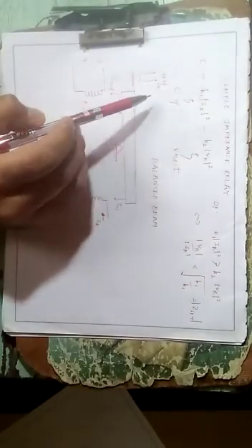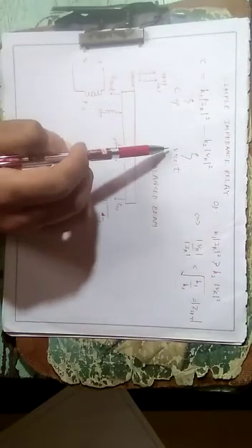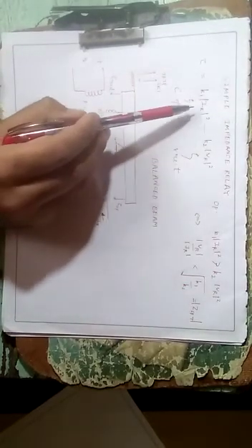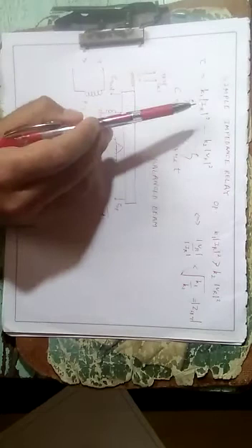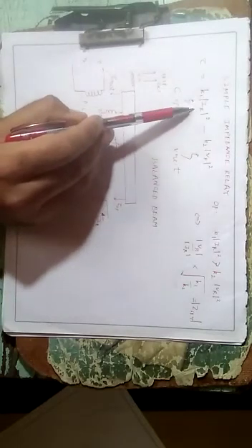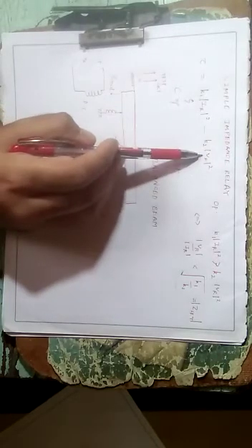Okay, so let us look at the simple impedance relay in some detail. We know that a simple impedance relay is basically a current operated voltage restraint relay. So it has two operating variables. It requires a current as well as a voltage. The current is supplied by a CT, the voltage is supplied by a PT, potential transformer. The basic operating equation is written here.